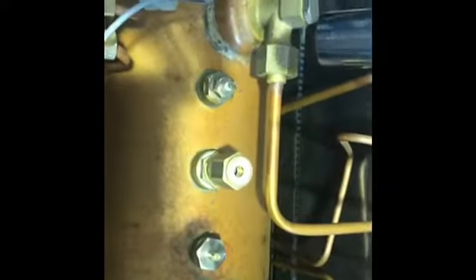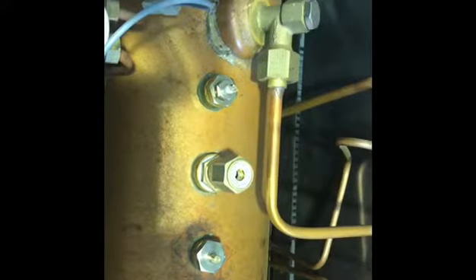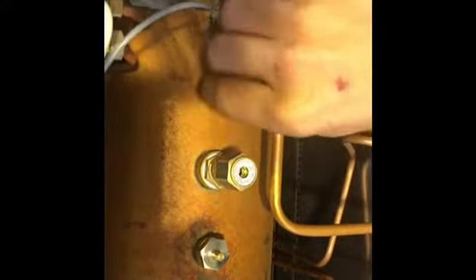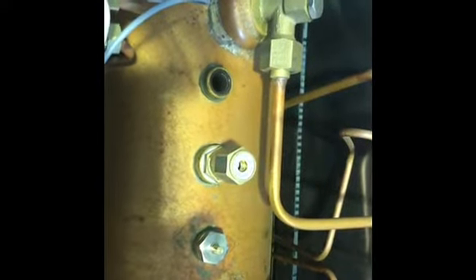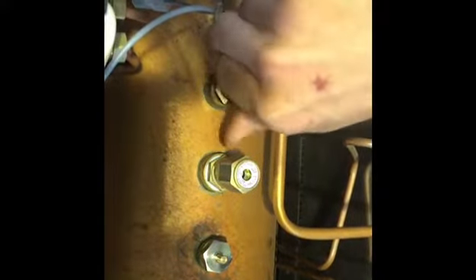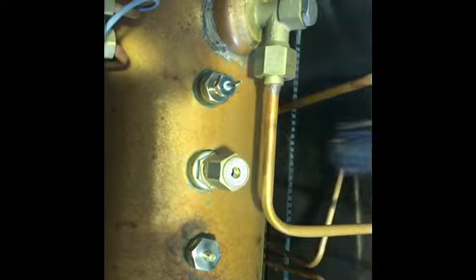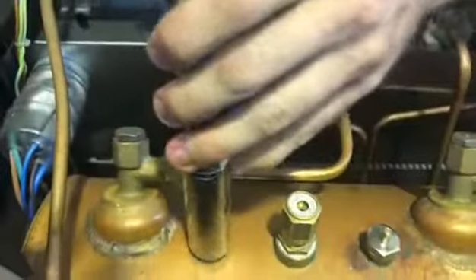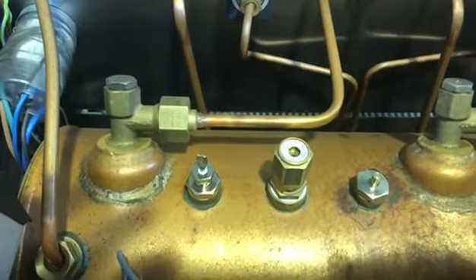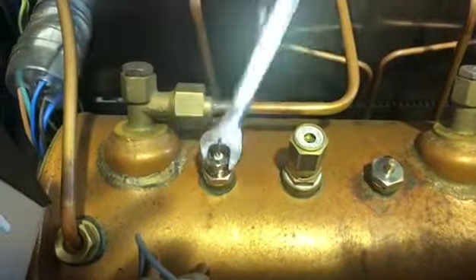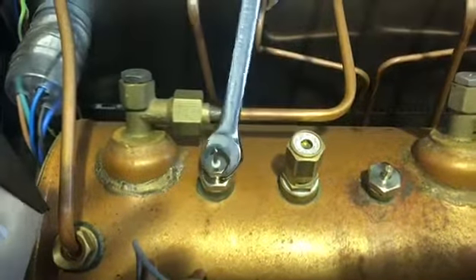The level probe is the second item that we'll replace. The cable comes off. Level probe is unscrewed and removed. And the new one is placed in. Once the level probe is tightened and in place, it's important that you tighten the top portion of the nut so that the level probe can't physically move.